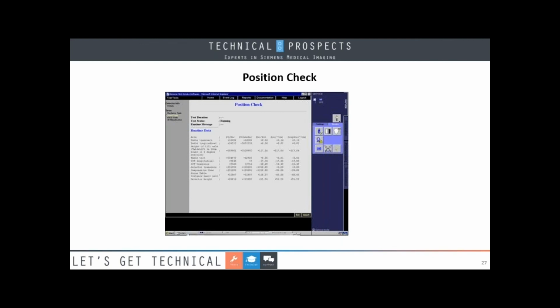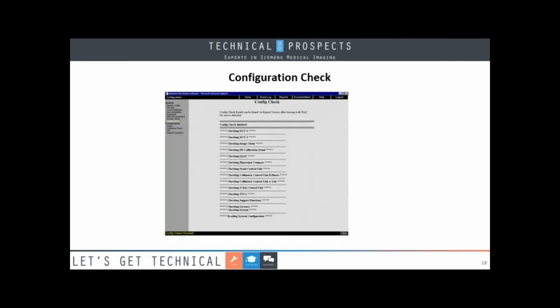Another basic check is configuration. You can see what's reporting back and what's listed, and compare it with what should be there. If a component isn't reporting back, you should check power to that component. What's nice is that it all populates automatically—it goes out and asks, are you out there, tube? Are you with me, detector? It goes through everything, and if it answers back, at least you know you have power and communication to the component.